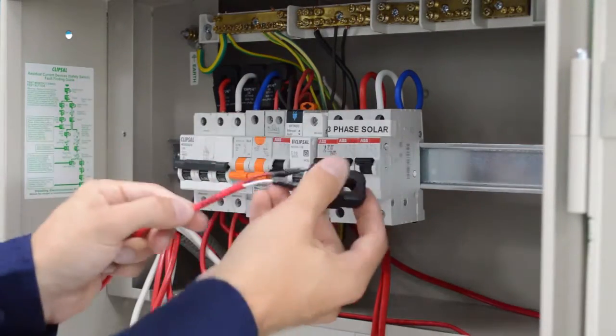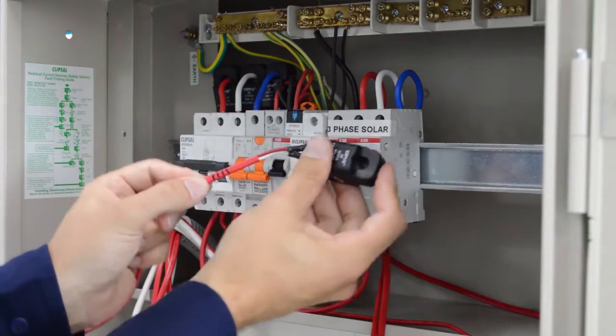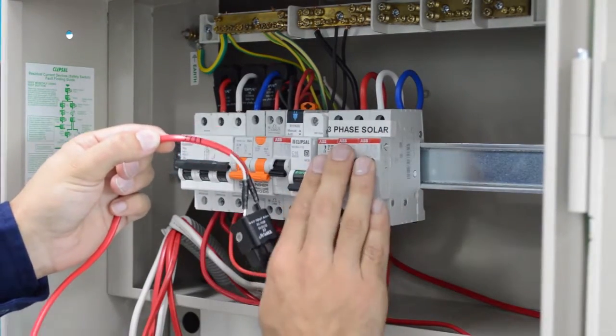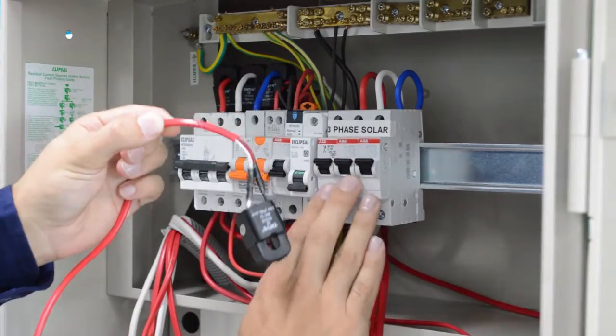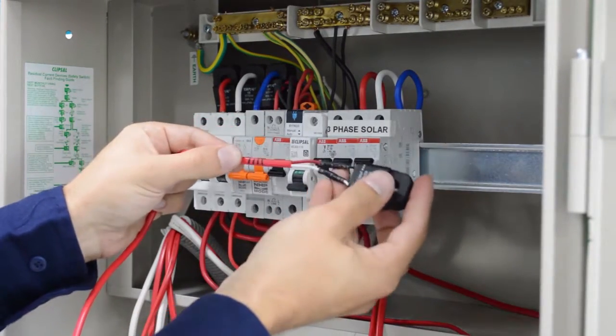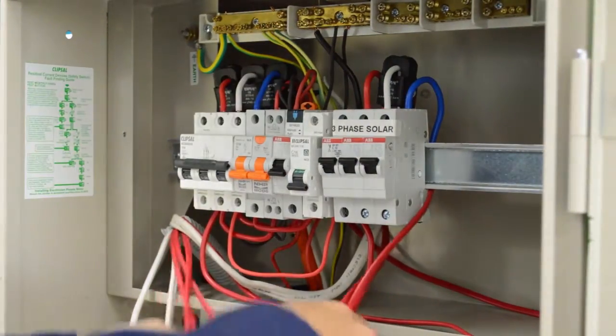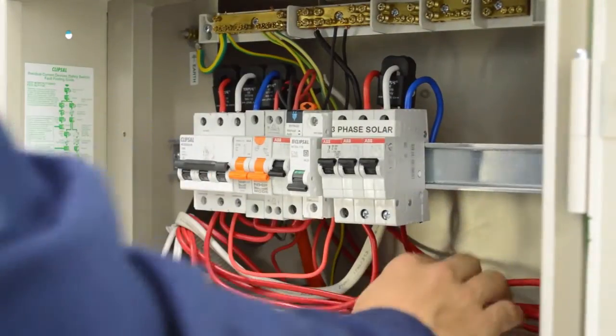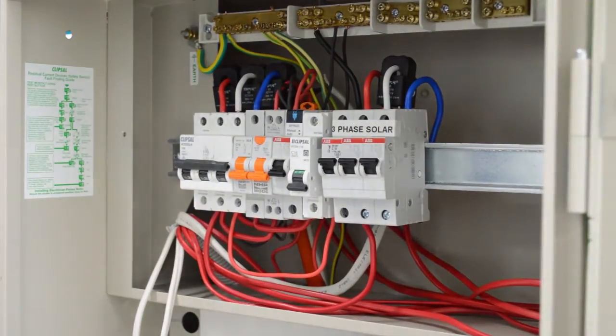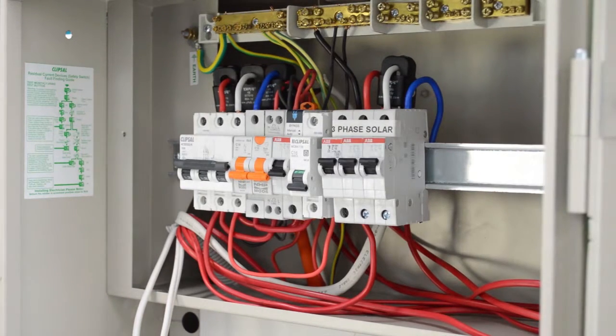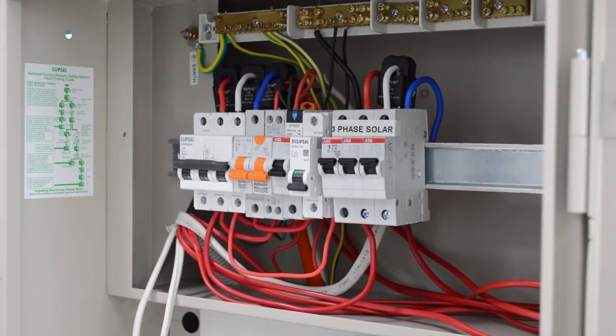We're now going to clamp the solar clamp around the solar active. It is important to take note that we have powered off the white phase and we have clamped the first mains active clamp around the white phase. Therefore, when clamping around the solar, you must clamp the single solar clamp around the white phase also. We use 1 solar clamp to clamp around 3-phase solar because every solar inverter has a balanced output, and we will multiply these readings later on in the commissioning process.